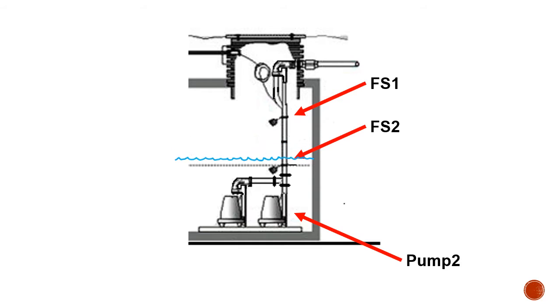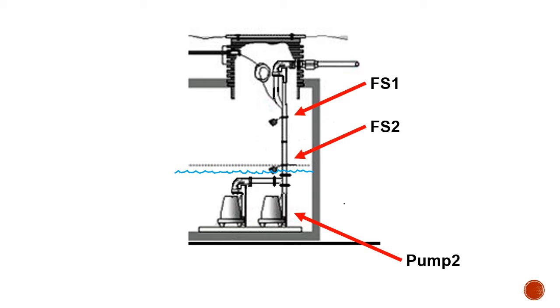Now on the next cycle when the water comes up, float switch one will then turn on pump two. And again as the water goes down, the second float switch will turn pump two off. And I want to have this sequence repeat itself over and over again where I'm flipping and flopping between the two pumps. You could use this in other applications, maybe you have a couple of grain silos feeding a burner and as one silo empties you'll want to automatically flip over to another silo. And that gives you a chance to refill it and then have it flop back once the second one empties back to the first. So how would we program this? Well let's take a look.